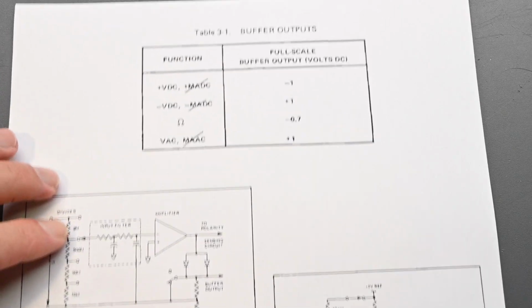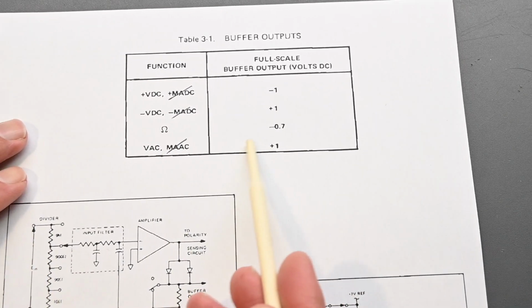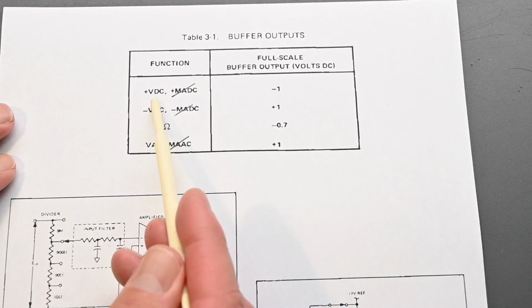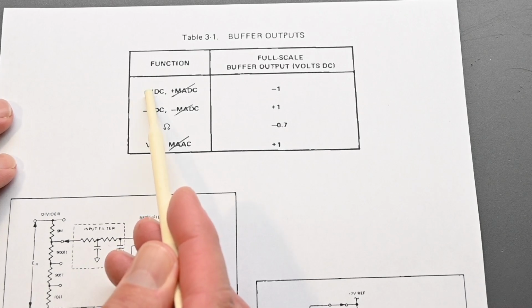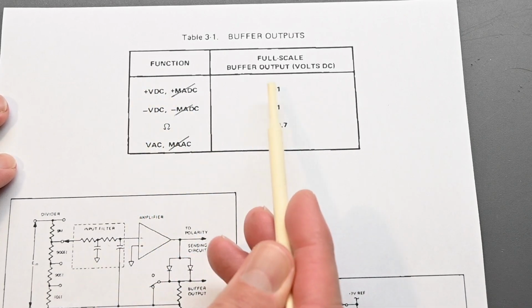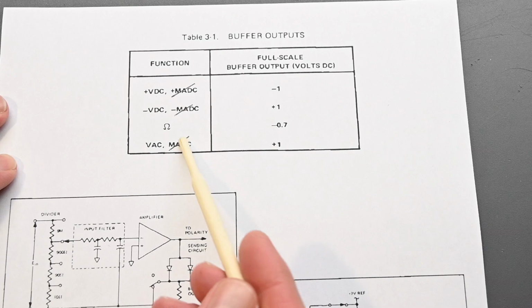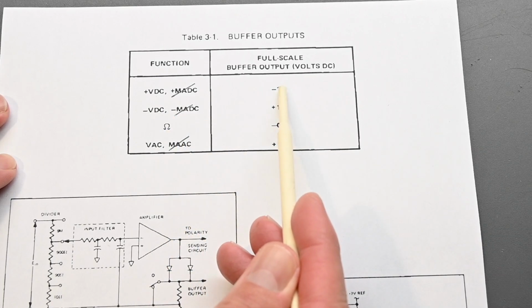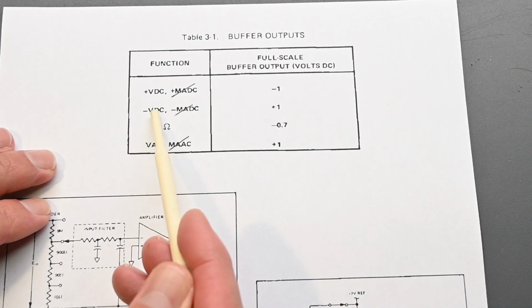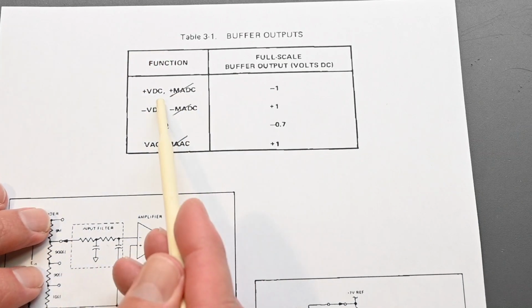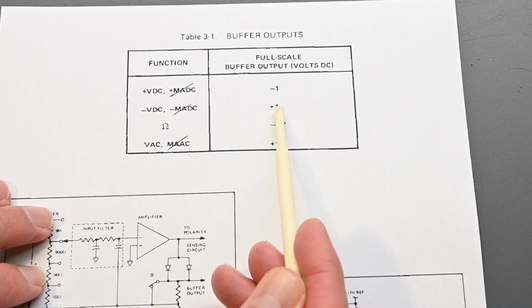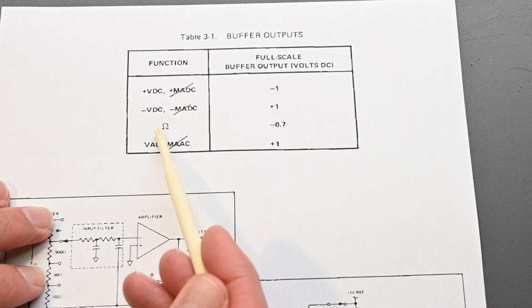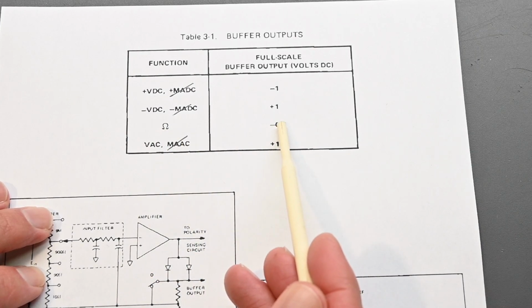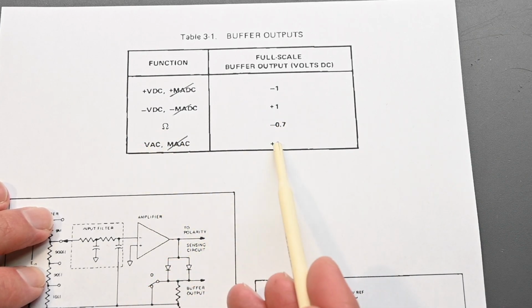All right, let's take a look at this next block diagram right here. So this is just a table summarizing that buffer output. So you can see in positive volts DC function, you're actually getting a -1 volt. It inverts it because of an amplifier. That's going into the analog to digital converter. The negative DC volt input, if you have the polarity flipped on the front panel, you're getting a +1 volt full scale into the converter. In the ohms range, -0.7 volts full scale, volts AC +1 volt.